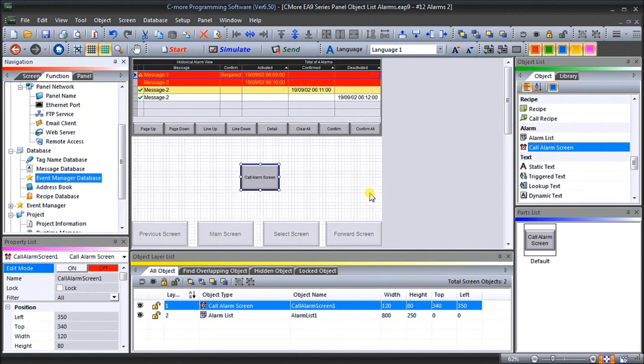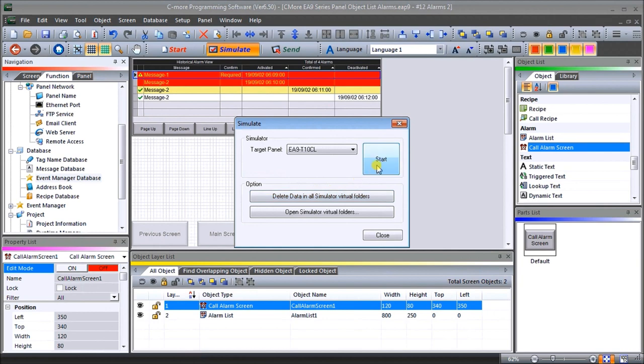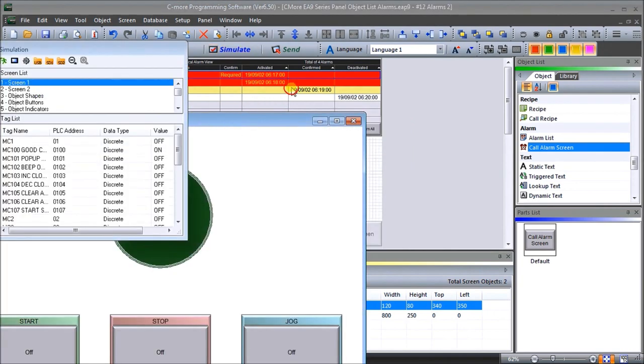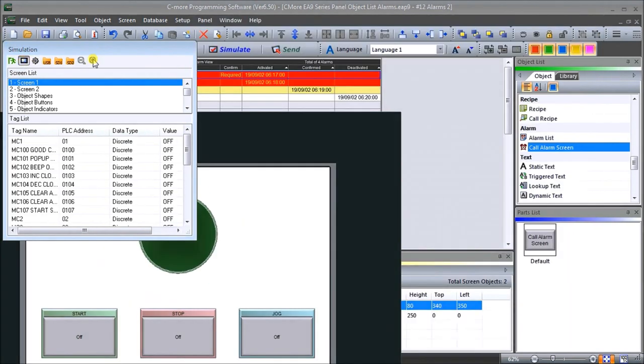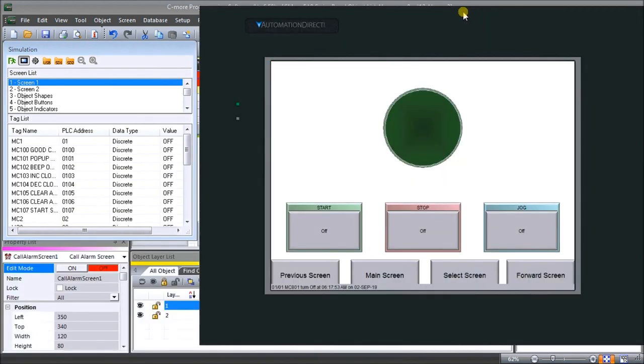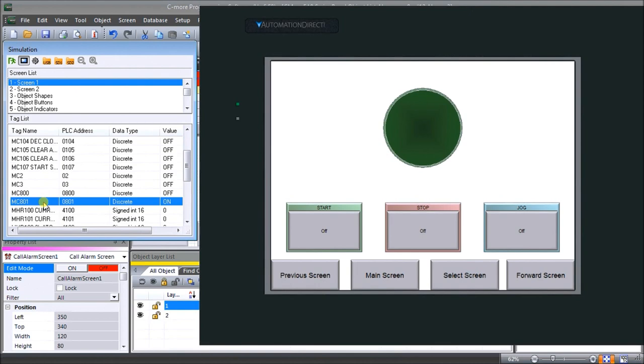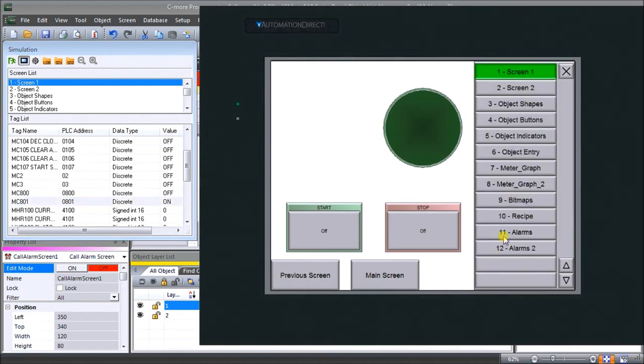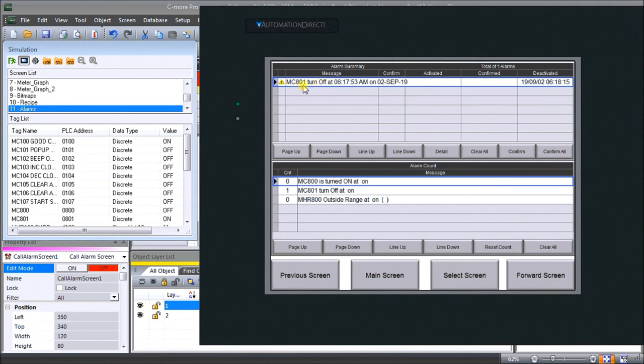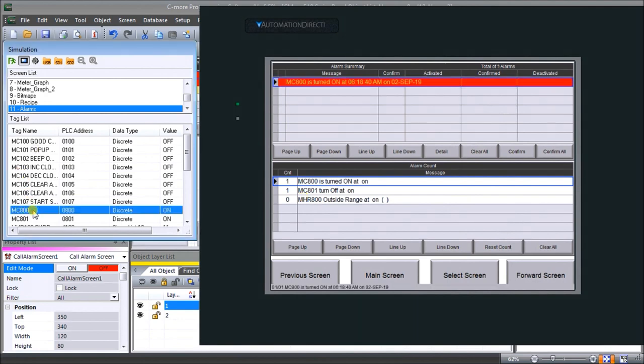Before we transfer to our HMI unit, we'll simulate this program — hit 'simulation start'. Here is our simulation with the bezel around it so it looks like our actual unit. We can see our display; let's turn that unit display off. Now if we go to the select screen and go into alarms, we can see that 'bit 2 turned off at this time'. We can confirm that — confirmed at that time — then confirm all, then clear all. Under alarm history we see bit 1 turned off.